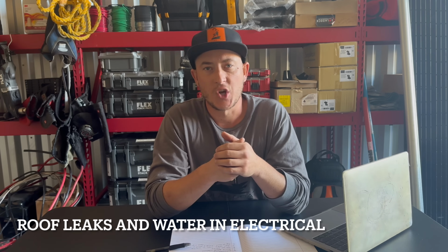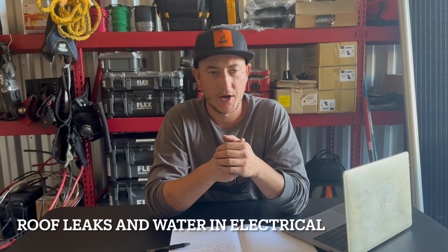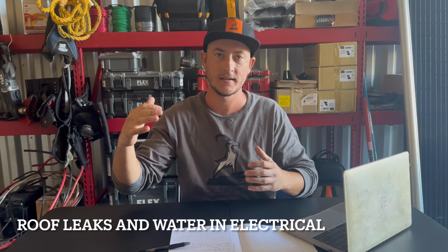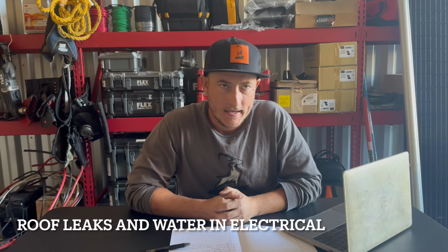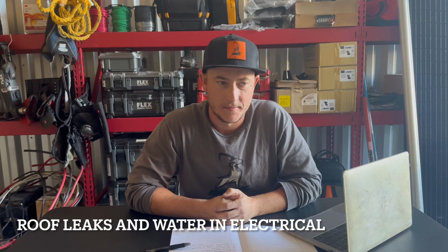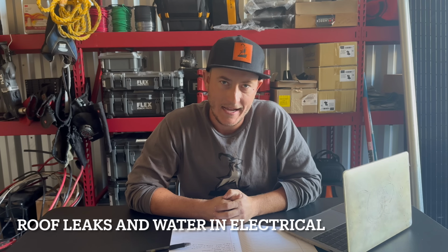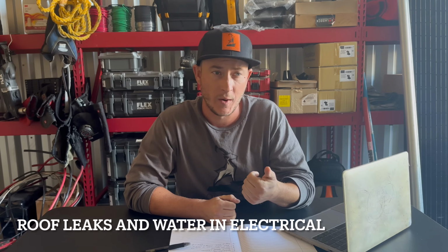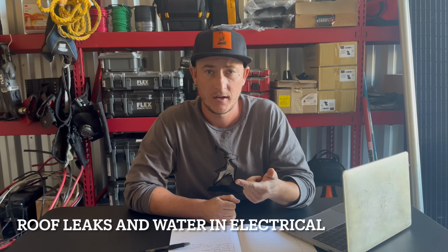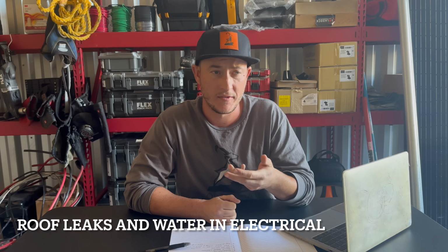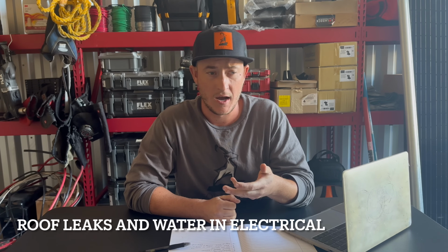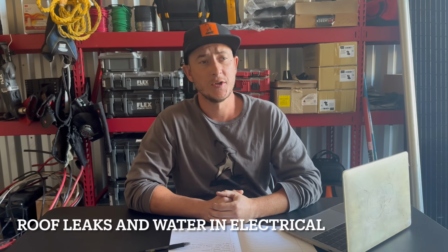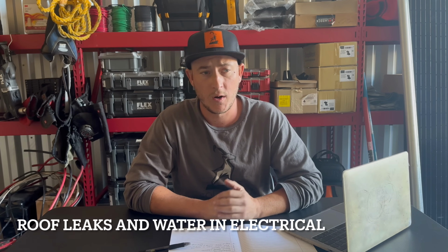I'm located in Salt Lake City, Utah. We have a pretty harsh climate where we get a lot of snow and rain, and then we get a lot of heat. I see a lot of solar panel systems fail because of water, ice and water, whether it's attachments leaking on the roof, water inside the conduit, water in the inverter, water in the junction box, whatever that is, water is the death of solar. And so you need to be very careful on how you're running your conduit.